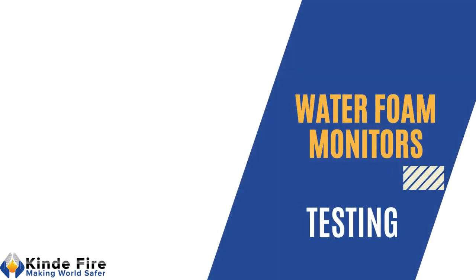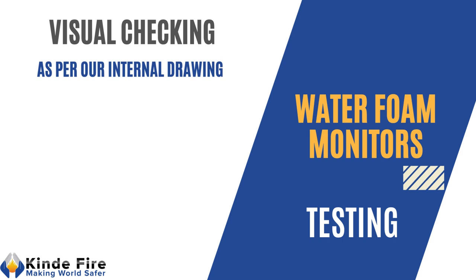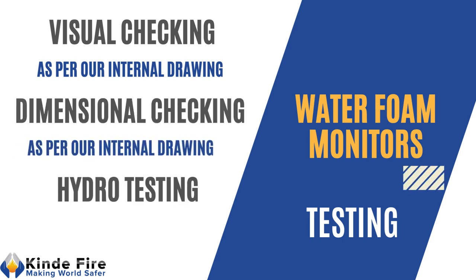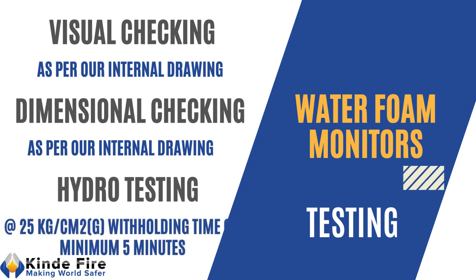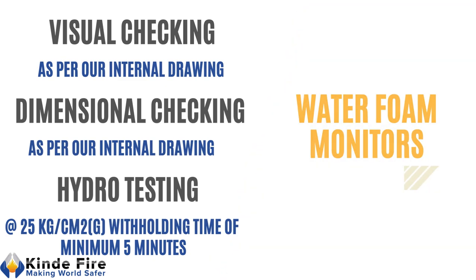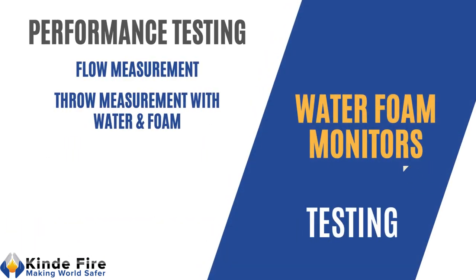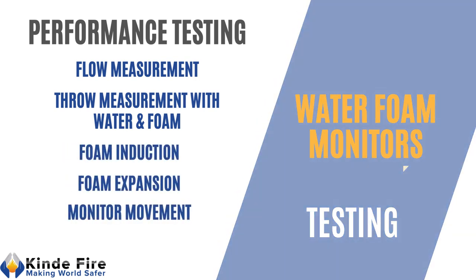Internal testing before supply: visual check as per our internal drawing, dimension check as per our internal drawing, hydro testing of foam monitor without nozzle at 25 kg per cm² with holding time of minimum 5 minutes. Performance testing shall be carried out to check flow, throw with water and foam, foam induction, foam expansion, and monitor horizontal and vertical movement.